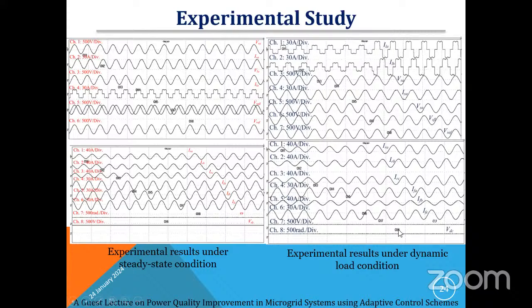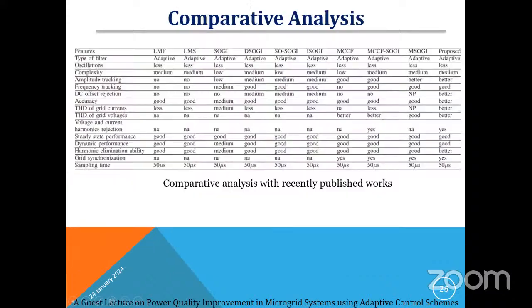In the second condition, the dynamic load condition, we have taken this result. Up to this point the load is constant. At this point, we have added an additional load to check the performance. In this performance also, the current THD is less than 5%, and these are the internal characteristics of the controller.